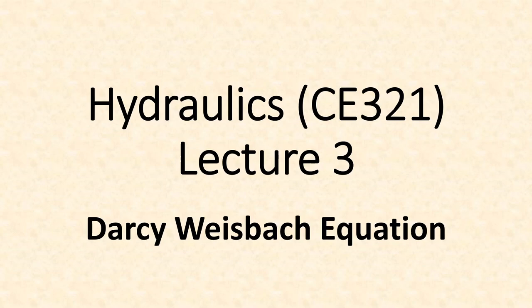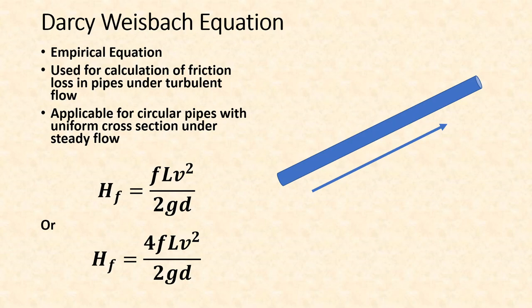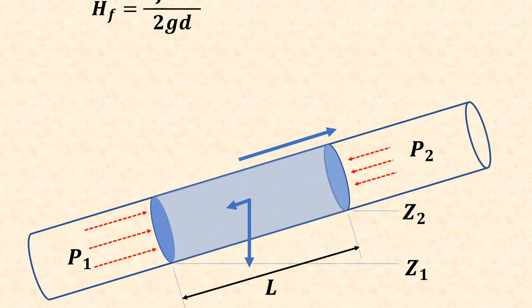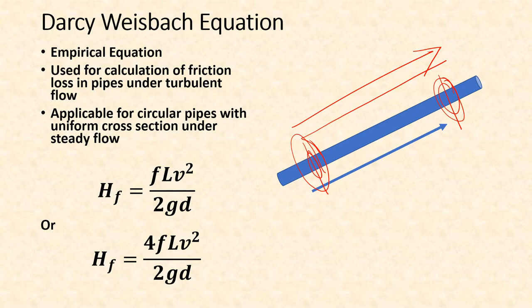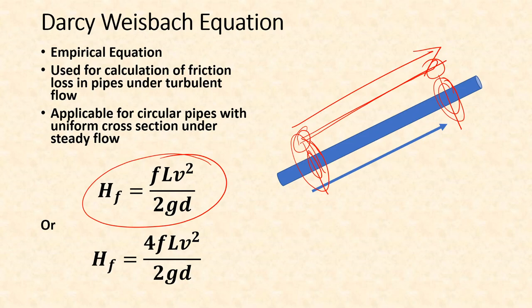In this lecture we are going to derive and discuss the Darcy-Weisbach equation. This is an empirical equation used for calculation of friction loss in pipes under turbulent flow. By friction loss we mean the loss of head between two cross-sections. If you measure the head at two cross-sections and flow is taking place in one direction, the head at the downstream cross-section is slightly less, and this difference is given by hf = flv²/2gd or 4flv²/2gd, where f represents different things in each form.